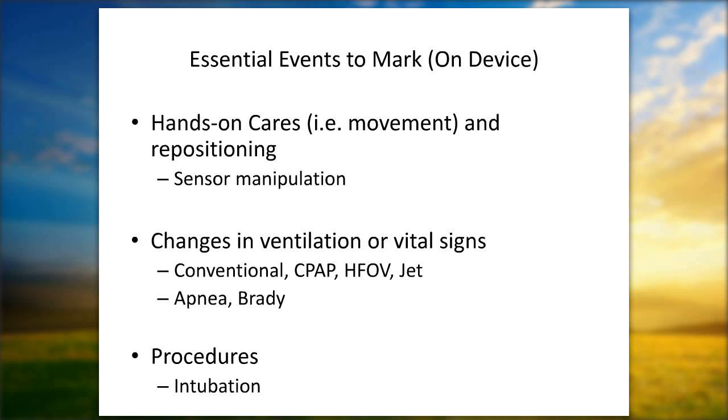I also do see that when people do position changes when babies are on high frequency, it's not uncommon to see that jiggle artifact shifting from one side to the other as the infants reposition from left to right, or maybe more midline and supine. So it's helpful, especially if you're changing and taking off or adding different ventilatory strategies. It sometimes does create artifacts, which it might be helpful to have noted.